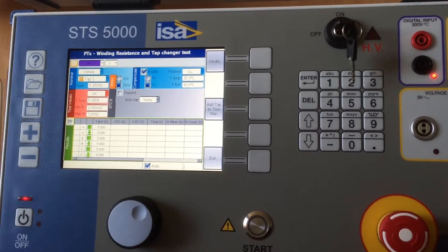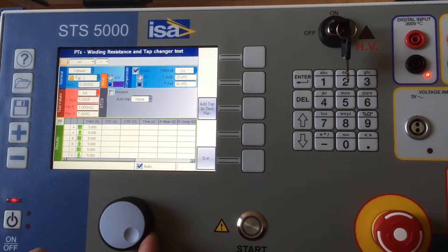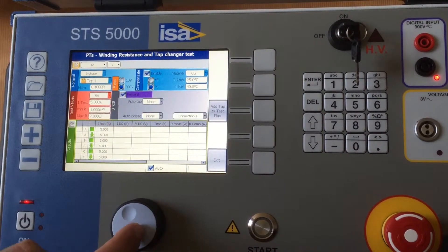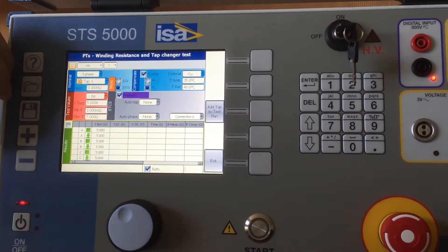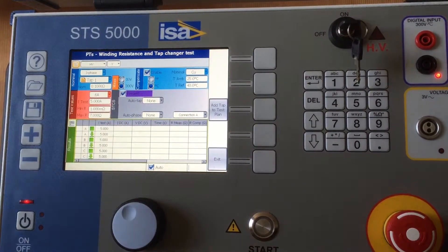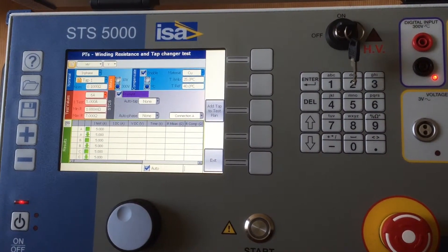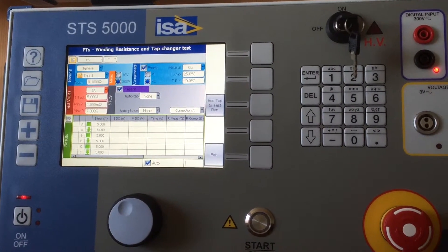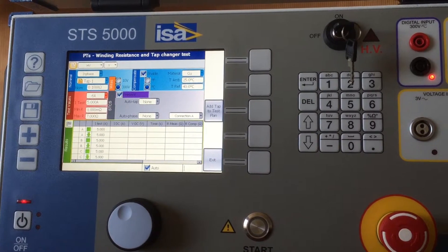Winding resistance is another test where you can use STS. As you can see, this is an automatic application. When I say automatic, I mean that this application can not only read and measure the static winding resistance — it also measures the dynamic winding resistance, which means it measures the resistance while the tap changer is changing position.